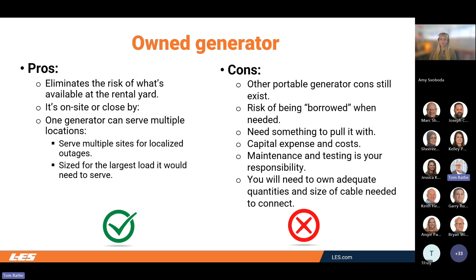Maintenance and testing is now back in your court, your responsibility, just like that permanently installed generator. You're back to having the capital expense and cost of ownership as well. And again, you've got to remember those cables, because these are very specific cables - you're going to have adequately sized cables of the length necessary to connect that generator to its worst case location.